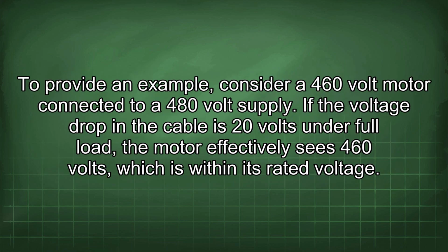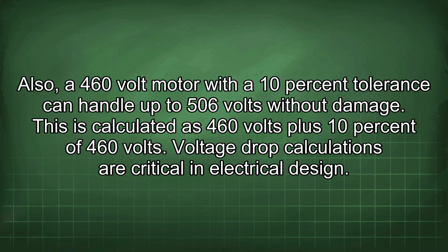To provide an example, consider a 460-volt motor connected to a 480-volt supply. If the voltage drop in the cable is 20 volts under full load, the motor effectively sees 460 volts, which is within its rated voltage. Also, a 460-volt motor with a 10% tolerance can handle up to 506 volts without damage. This is calculated as 460 volts plus 10% of 460 volts.